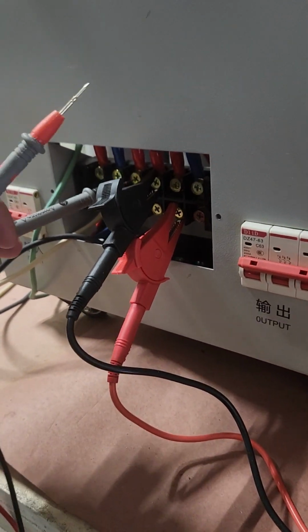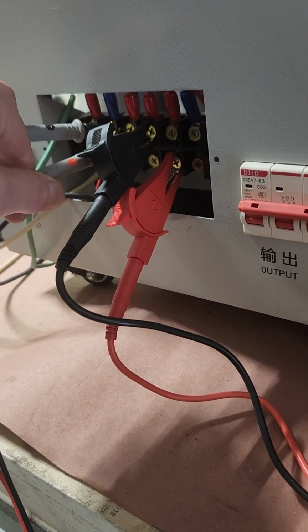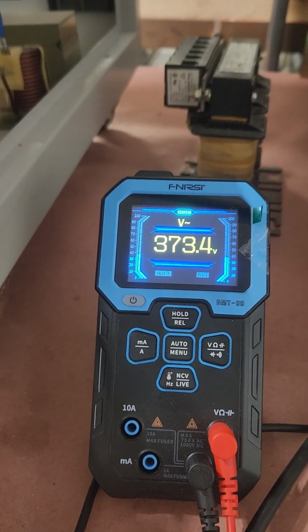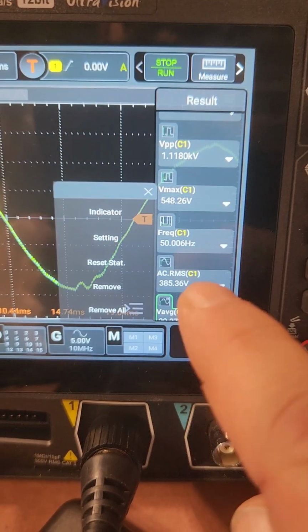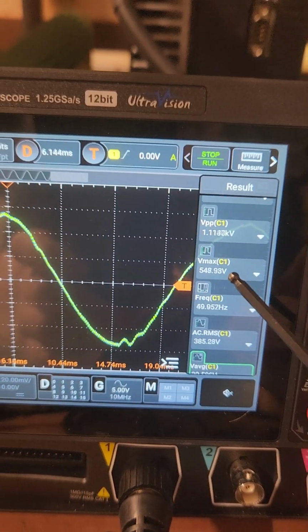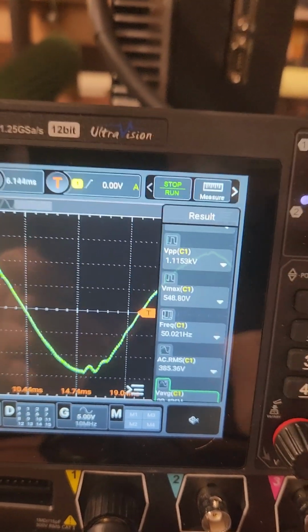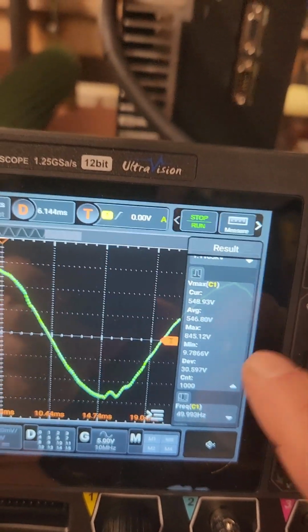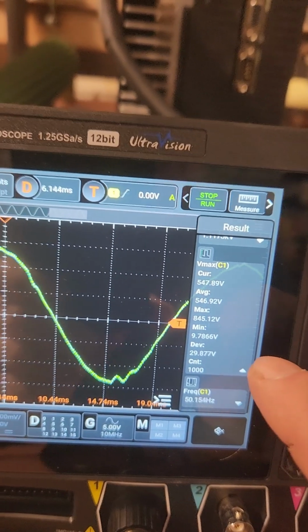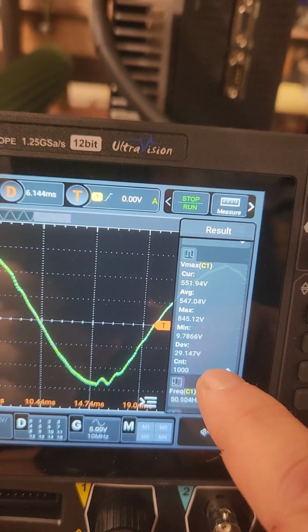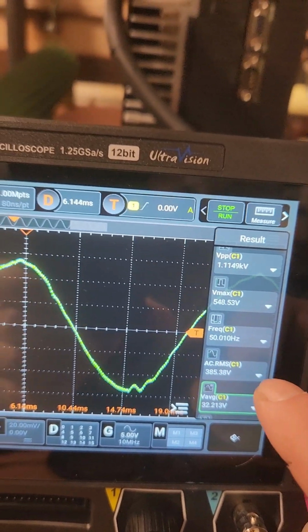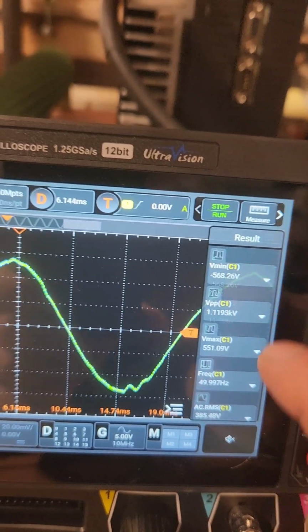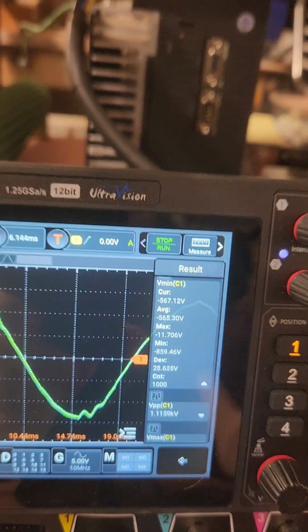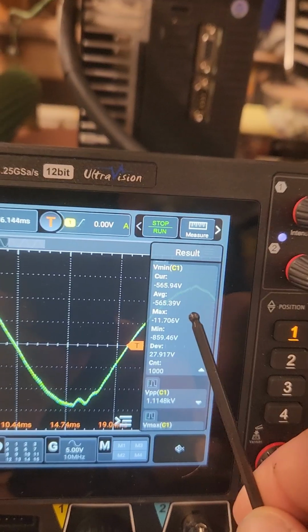But anyway, here's what my multimeter shows me. So I'm gonna put that into, see if I can do it without electrocuting myself. Right, so it's not 360 what I said, it's a little bit higher, 370, and it's similar for the other one. And this guy reports here RMS 385 volts. So yeah, that's close to 380 what I need. But the peaks are no longer 580 volts, right? It's 540 something. If you look here at the average is 546. So I dropped that peak at 580 volts. And that's average, right, over 1,000 waves. And then similarly the V minimum, where is that? This guy is 565, right, from 580. So it's much better.